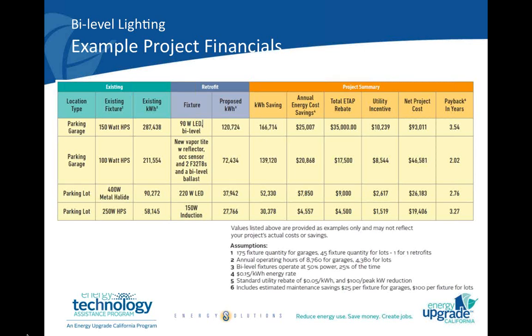So to give you a typical idea of project energy savings and financials, there's a table. This table shows a few different scenarios. I'm going to walk through the first line item. All these scenarios are based on a 175 fixture quantity in the garage. So the first line item shows that the existing fixture is a 150-watt high-pressure sodium fixture with an estimated existing annual energy use of just under 300,000 kilowatt hours per year. With the retrofit fixture, we have a recommended 90-watt LED that's bi-level capable, so it can reduce to at least 50% of the wattage when nobody is present, which is estimated to use around 120,000 kWh per year. So right there alone, you have over a 50% reduction in energy use.